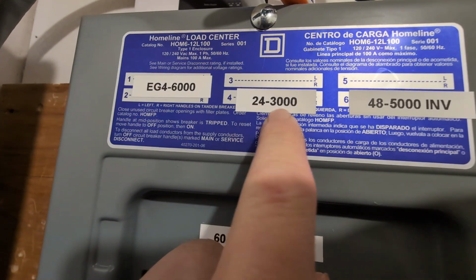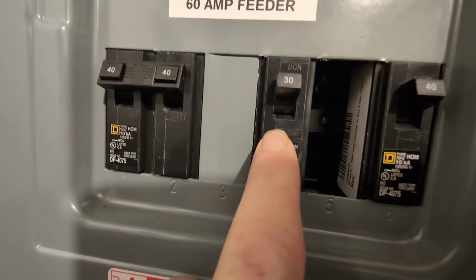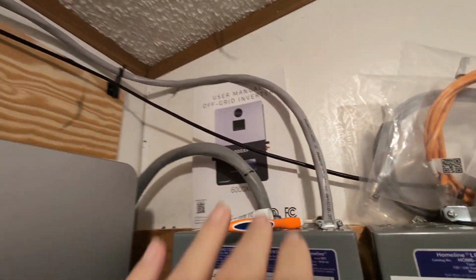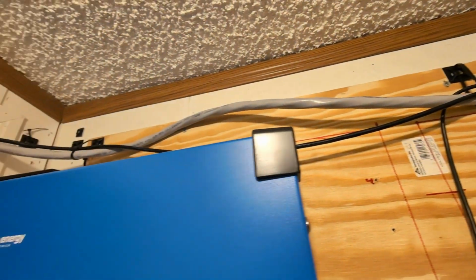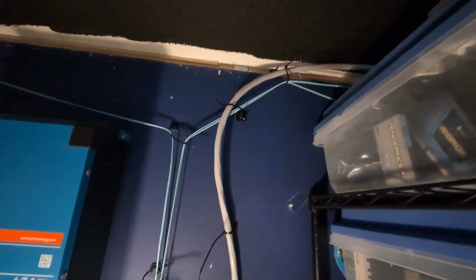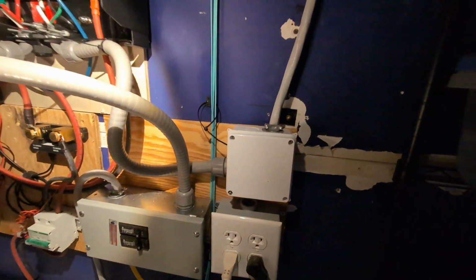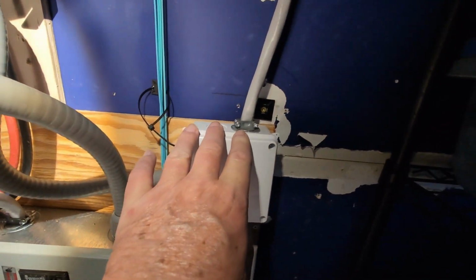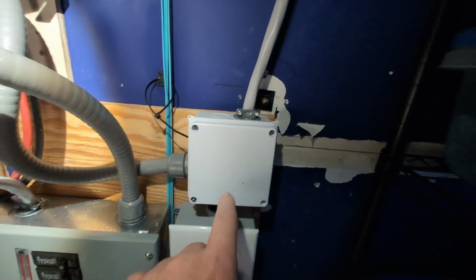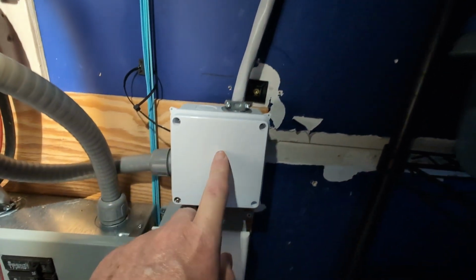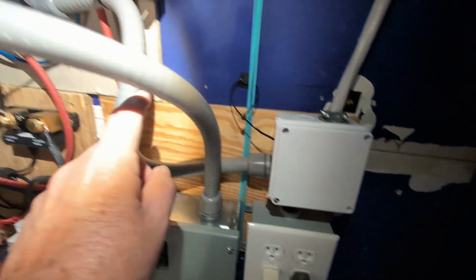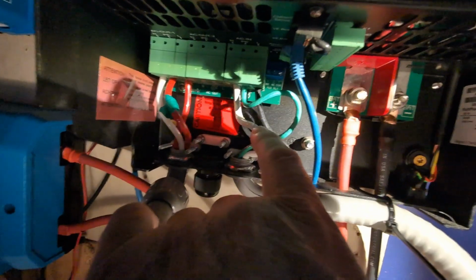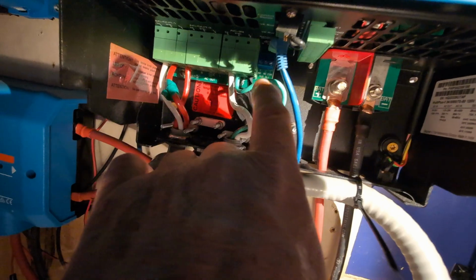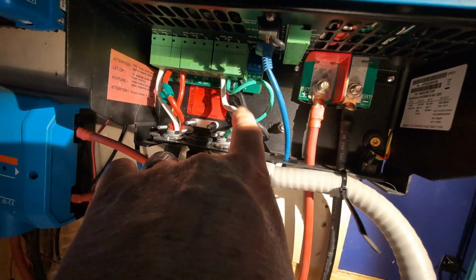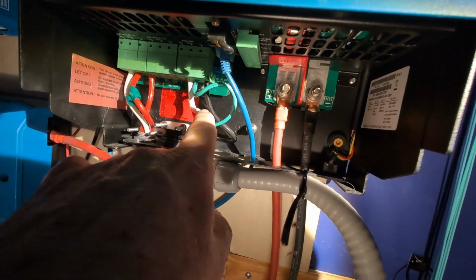Then for the 24 volt 3000 VA inverter from Victron, power is a 30 amp breaker, and that goes up through this cable here, which then goes along the top of the equipment closet room. And then that wire feeds down the wall, providing grid power to this box, 120 volts at 30 amps. And then the wire is converted from aluminum to copper inside this box. And then number 6 copper wire is run up to the Victron, because the Victron will not accept aluminum wiring. So I wired that up through there. That's the grid coming in.